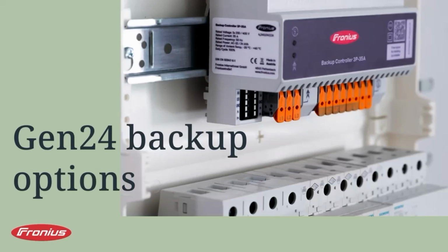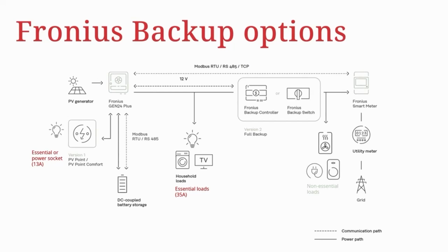So we have a number of different solutions available for Fronius backup, and it's important to understand the different topologies for these. We can have devices which are connected directly at the inverter. This is called our PV Point system. We could have a backup controller or switch which are installed just on essential loads within the property. Or we could look at a full household backup so that all loads are covered by the PV and backup system. So let's have a look at each one of those in turn.